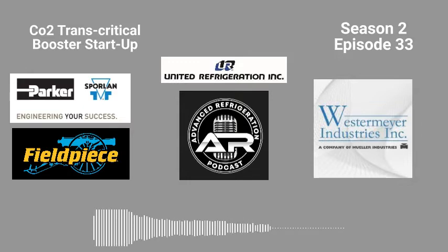I mean, the flash gas bypass valve, you really don't care so much about, because you're already pulling on the suction anyway. Yeah. But the drop leg, I mean, you can. I usually like to try, and I'm pulling on different sections, that I could throw the micron gauge on there and see where I'm getting my pressure drop at. But then I'll throw the micron gauge, one at the rack, and then one at one of the cases, and see where I got my good vacuum at.